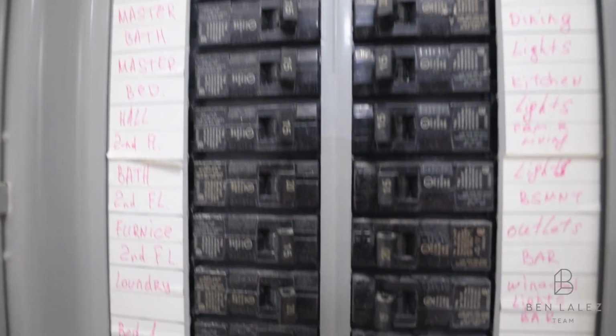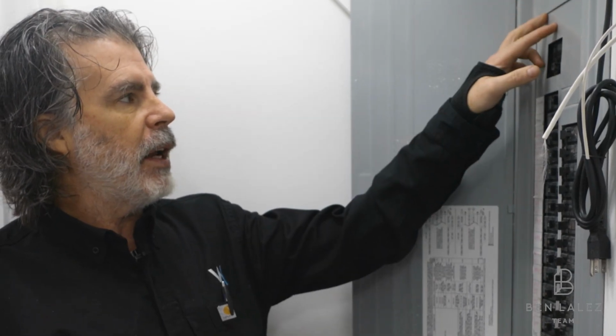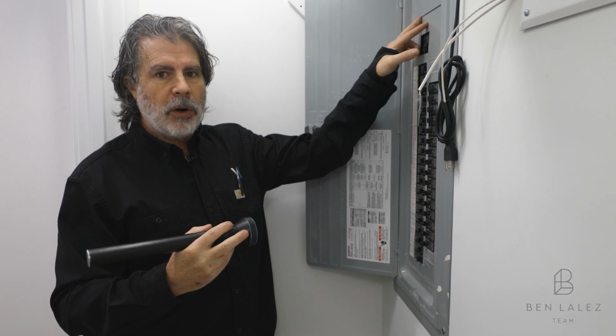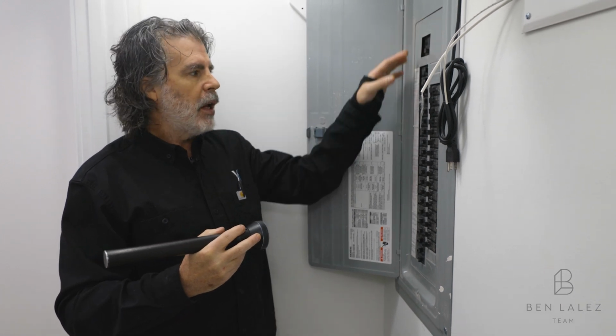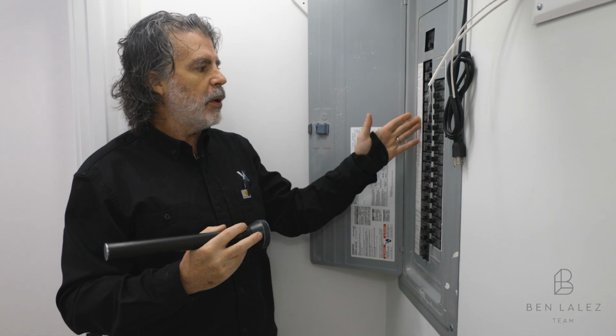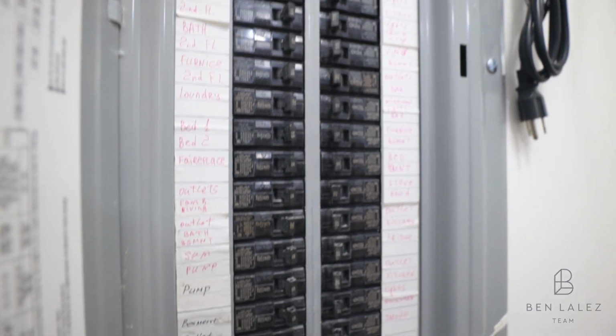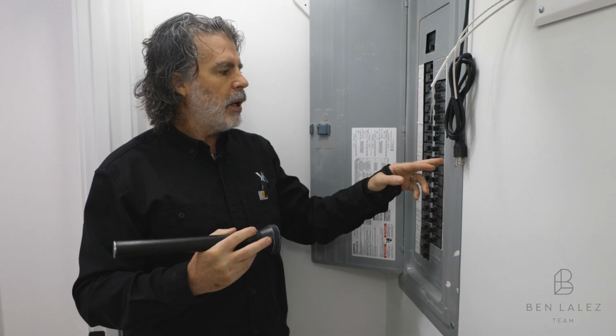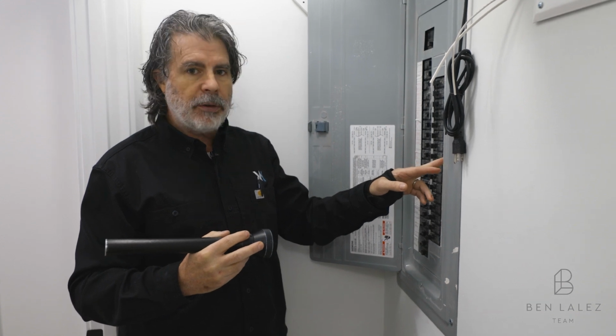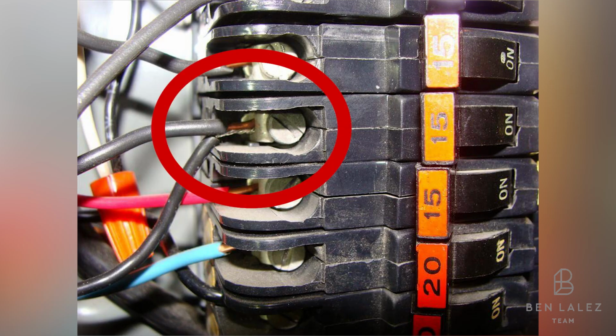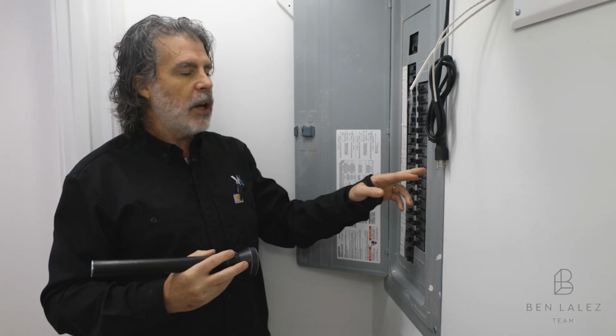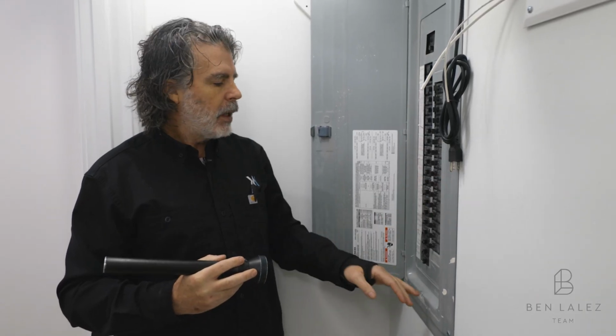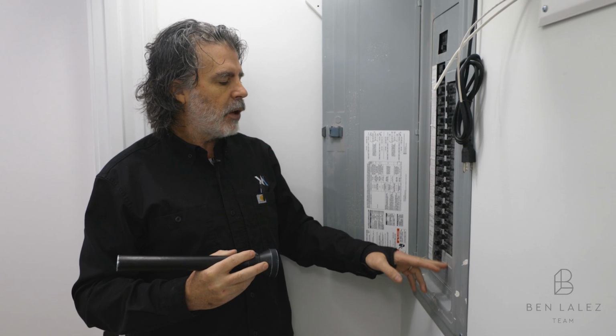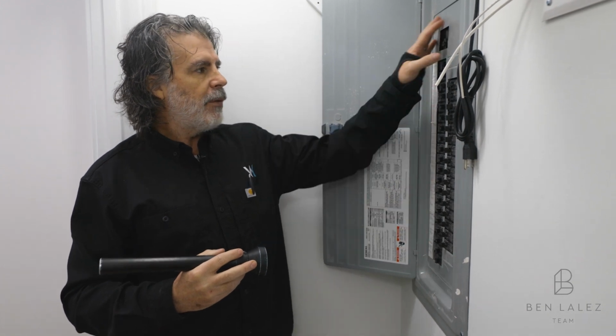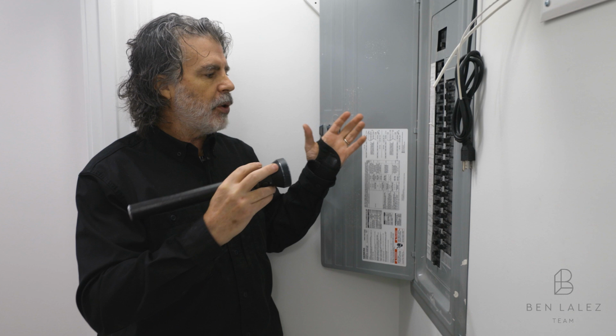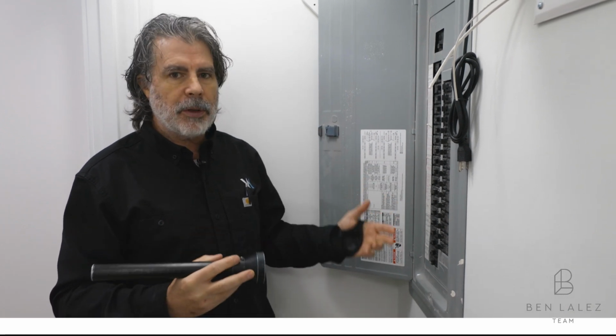I always take off the panel and I'm going to identify what the amperage is coming into the home, whether it's aluminum or copper. I also want to identify aluminum or copper for your branch. You don't want to have aluminum. Then I'm looking to make sure you don't have any undersized wires for your breakers or any double tapping, which would mean you'd have more than one wire per breaker. Now this panel is great because you have room for a couple more breakers and you never want to double tap before the main. I want to make sure that there's no signs of rust or moisture.